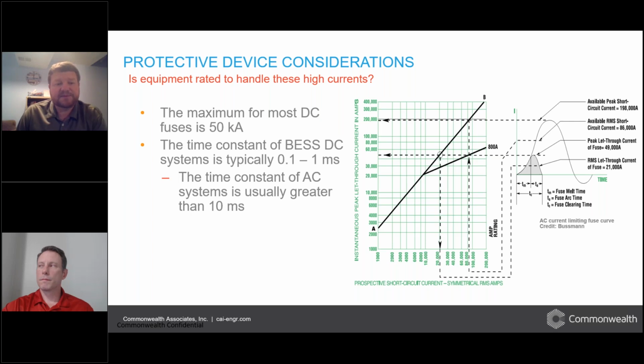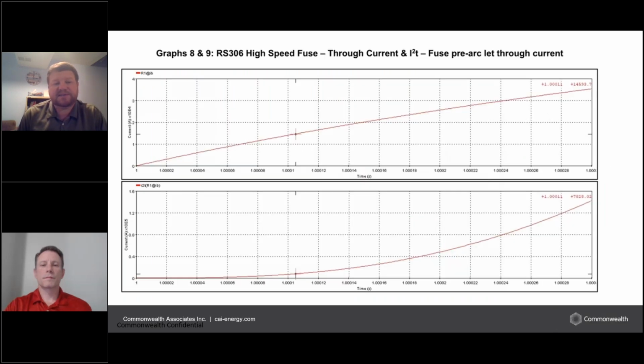So sometimes the use of AC current limiting device fuses can help me save a little bit of cost on my equipment ratings by making sure I have these devices in place, and I can use graphs like this provided by the current limiting fuse manufacturers to help select the fuse and then select any equipment that's downstream of that fuse. But this all depends on the idea that we have these constants in place that exist for AC systems that don't exist for the DC systems.